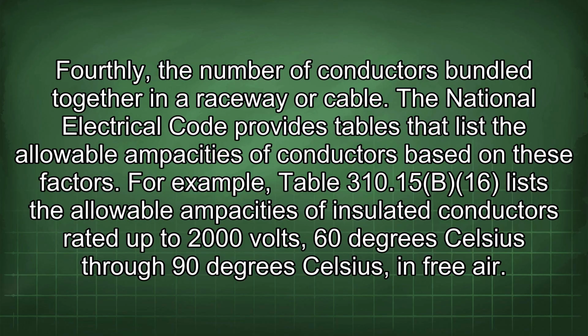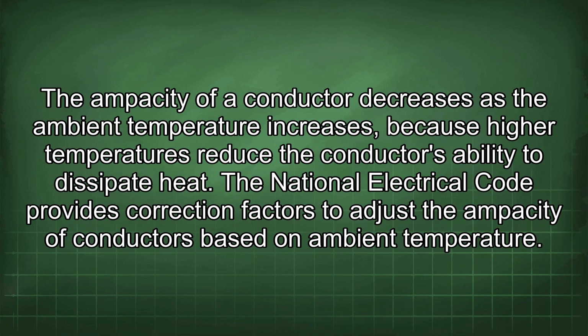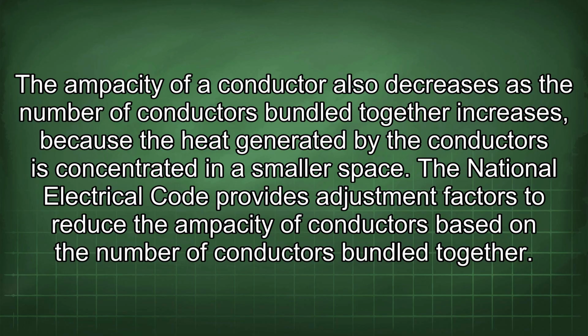The National Electrical Code provides tables that list the allowable ampacities of conductors based on these factors. For example, Table 310.15(B)(16) lists the allowable ampacities of insulated conductors rated up to 2000 volts, 60 degrees Celsius through 90 degrees Celsius, in free air. The ampacity of a conductor decreases as the ambient temperature increases because high temperatures reduce the conductor's ability to dissipate heat. The National Electrical Code provides correction factors to adjust the ampacity of conductors based on ambient temperature. The ampacity of a conductor also decreases as the number of conductors bundled together increases because the heat generated by the conductors is concentrated in a smaller space.